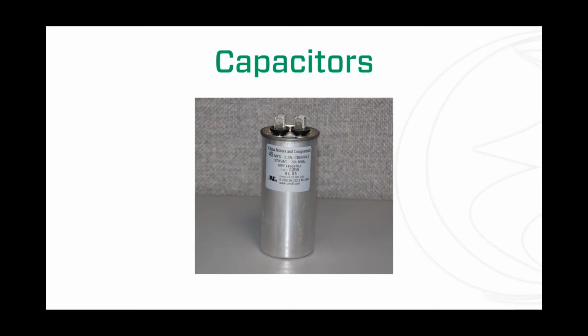If you purchase a new pump, one of our larger single phase pumps, it will come with a box taped to it that has a start capacitor, a run capacitor, and a relay inside. We recommend you change out these components every time you change out the pump, since these things have a service life and do go bad.